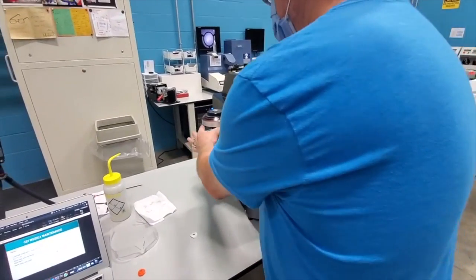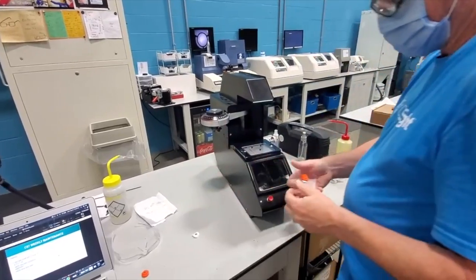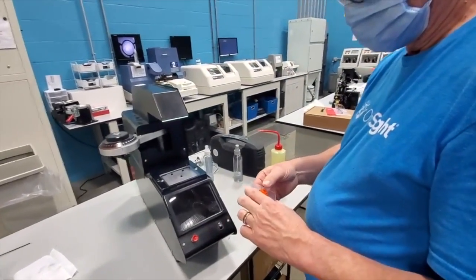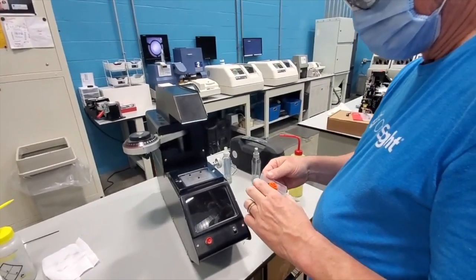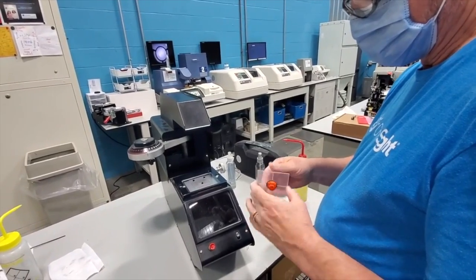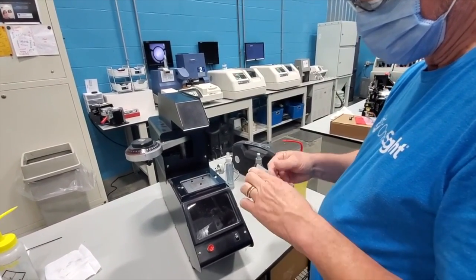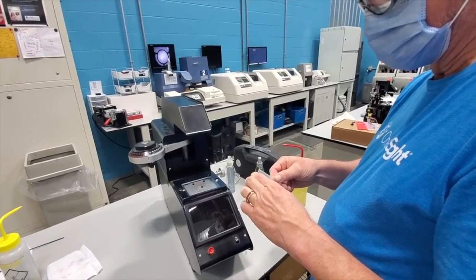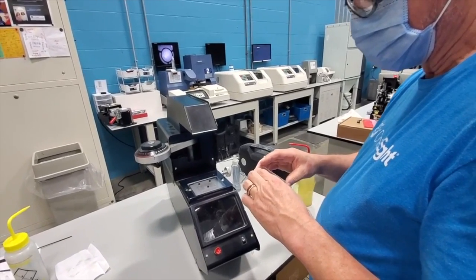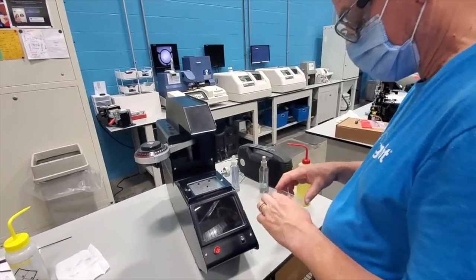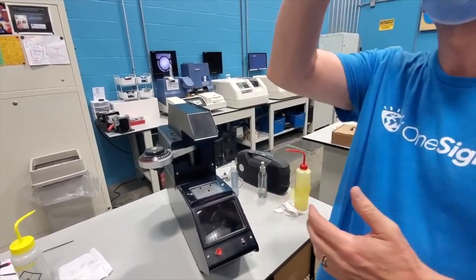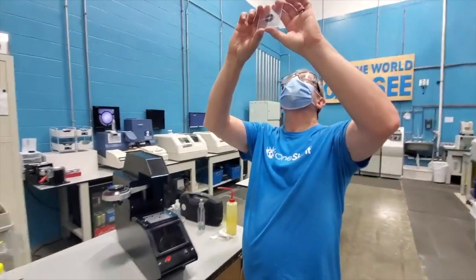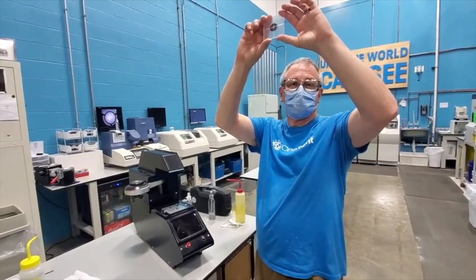And then he's going to go ahead and remove the calibration disc. Once you do this, there's a couple things that he's going to look for. On your block itself, you have lines that go horizontally as well as vertically. You're going to check and make sure that those line up. And then you're also going to look right through the center of the block, through the hole, to see if you can see the crosshair. So Mike's checking that right now, and then I'll show you guys what it looks like here in a second.